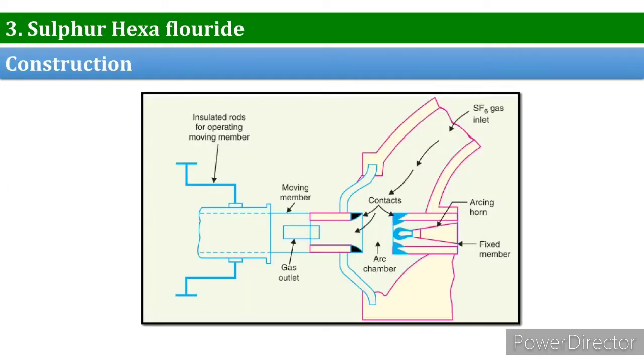Now we will discuss sulfur hexafluoride, commonly known as SF6, circuit breakers. As the name suggests, SF6 gas is used as the arc quenching medium. SF6 is an electronegative gas and has a strong tendency to absorb free electrons. The contacts of the breaker are opened in a high-pressure flow of SF6 gas and an arc is struck between them.